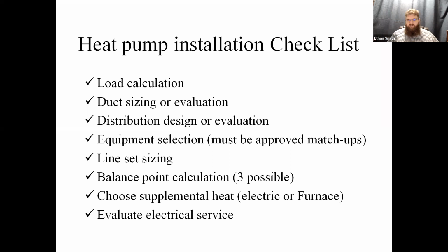We here at GA Larson have a particular policy that we do not use third-party heat pump coils on any of our sales anymore. We used to have a line of third-party heat pump compatible coils that we would sell with heat pumps. We found that we had more problems than it was worth, and so we dropped them, because occasionally the computer model that generates the matchup for that third-party coil just was not accurate, and it caused problems. But the OEM matchups almost always work flawlessly if they're installed properly. Other things we need to consider, guys: line set sizing. If you're reusing that old line set, make sure it's compatible, especially if they had an AC before. Make sure it's compatible with the heat pump, so that you're not setting yourself up for failure there.